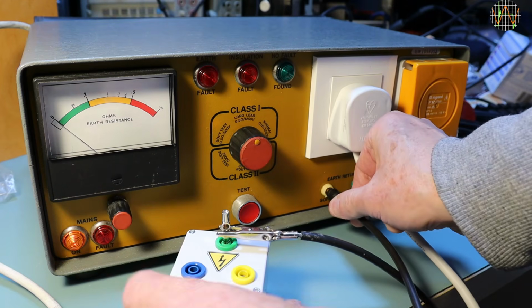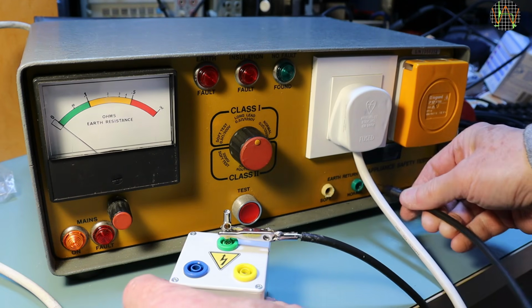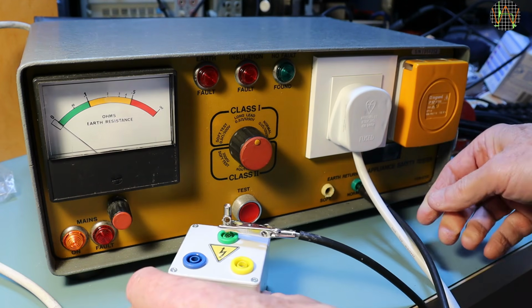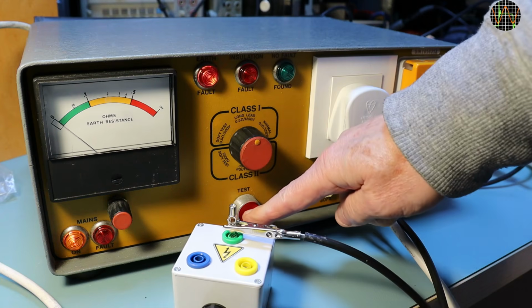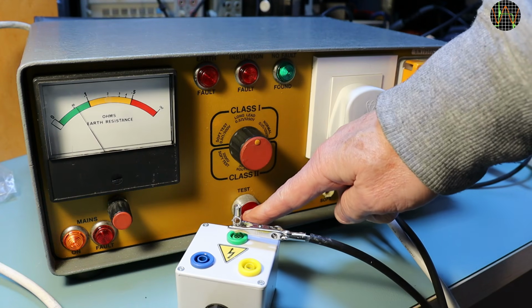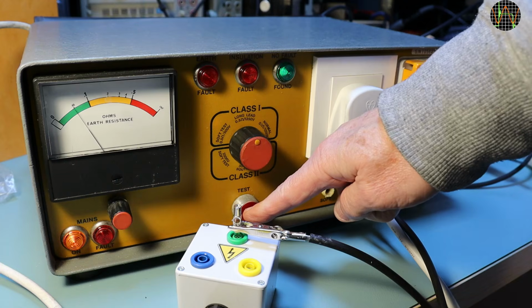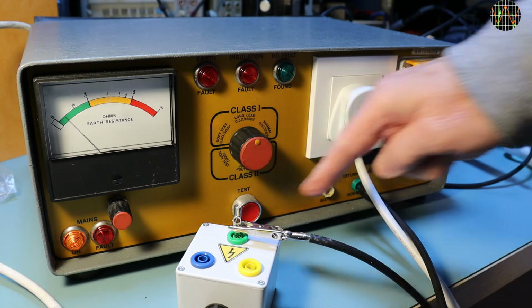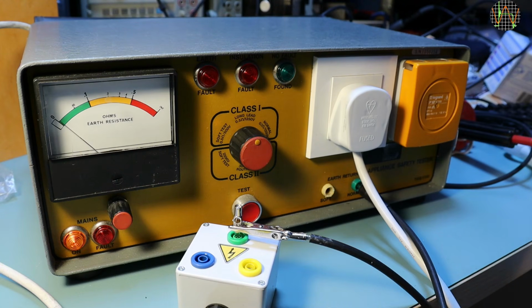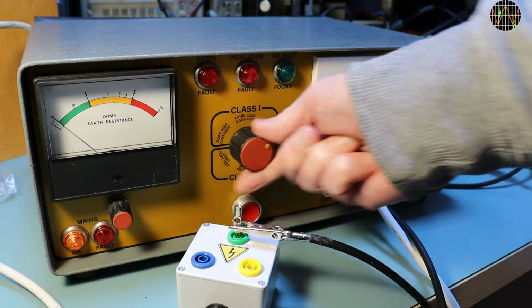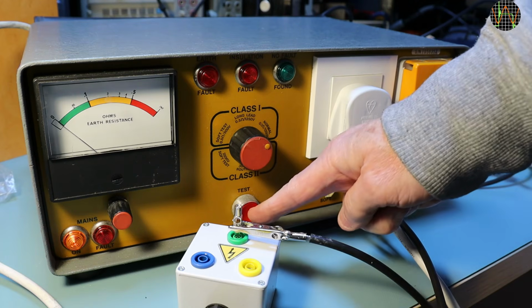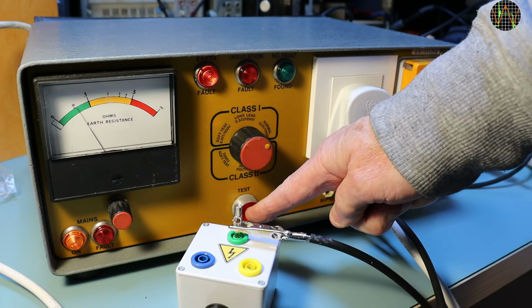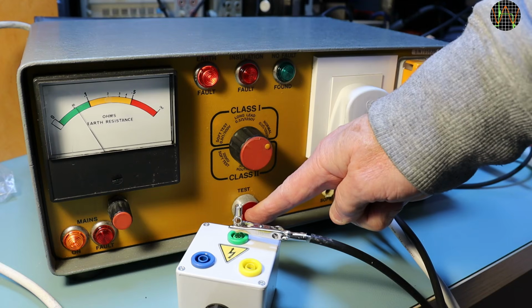Moving on to a proper test, but for items with long leads, for example a vacuum cleaner. I think the tester will treat any resistance below 0.5 ohm, basically anything not in the red zone, as okay for this test. It passes and the meter shows about 0.05 ohm, still well into the green zone. Moving to the normal setting, this reduces the tolerance to 0.1 ohm, basically the green zone only.